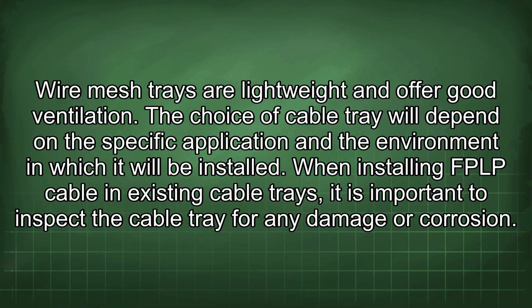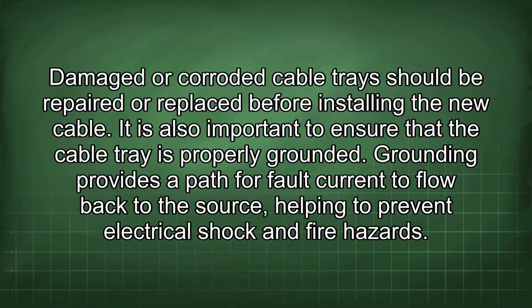When installing FPLP cable in existing cable trays, it is important to inspect the cable tray for any damage or corrosion. Damaged or corroded cable tray should be repaired or replaced before installing the new cable. It is also important to ensure that the cable tray is properly grounded. Grounding provides a path for fault current to flow back to the source, helping to prevent electrical shock and fire hazards.